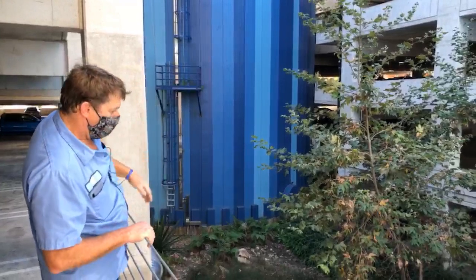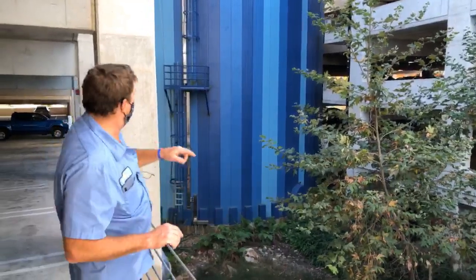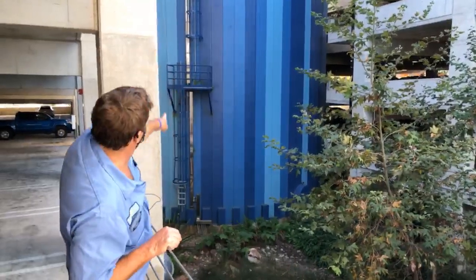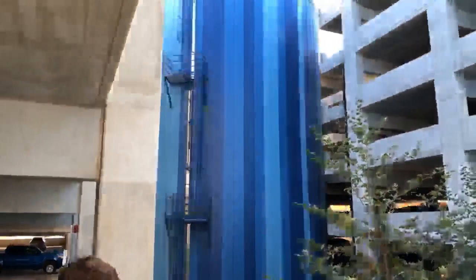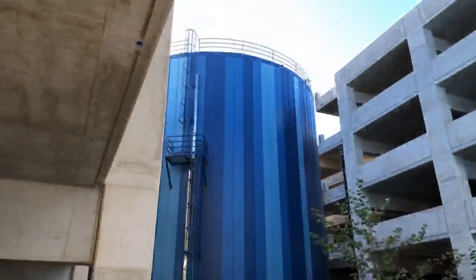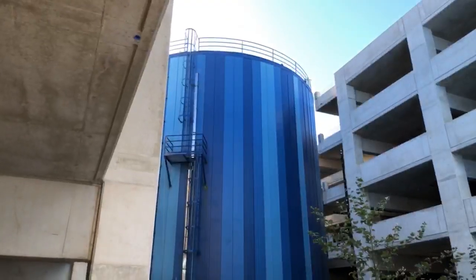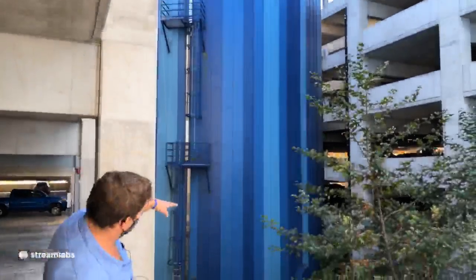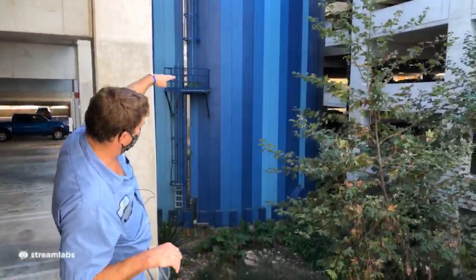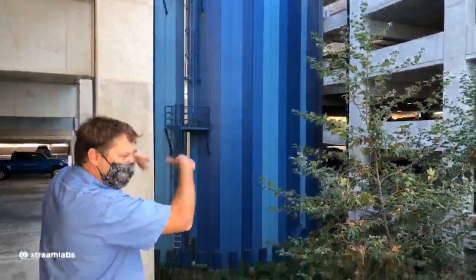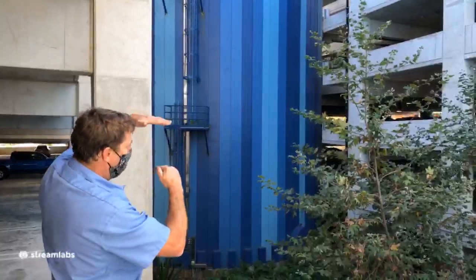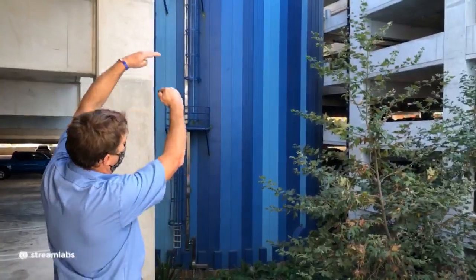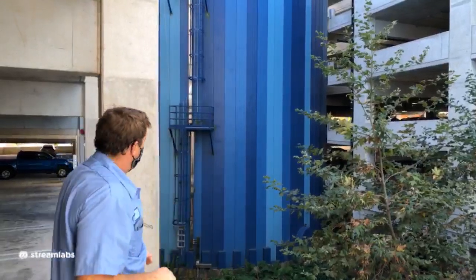You can see that because these are monitored over at Cogen. Inside those stainless steel boxes are nothing but temperature sensors every 2 feet, so we can see the thermocline, the term that tells us where the 40 stops and the 50 begins. As long as you don't mix it up, it's a pretty defined line, going up and down, 58 on top and 40 on the bottom.